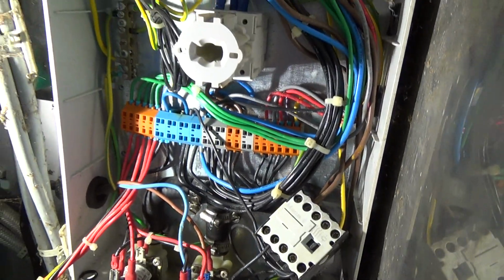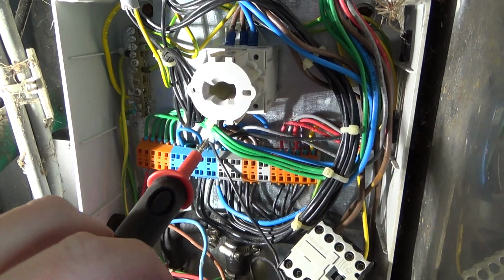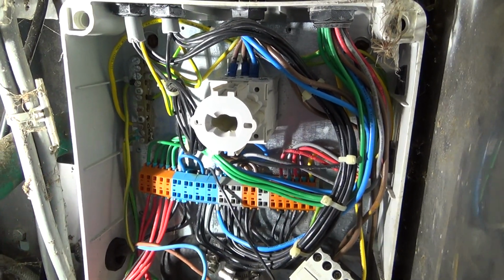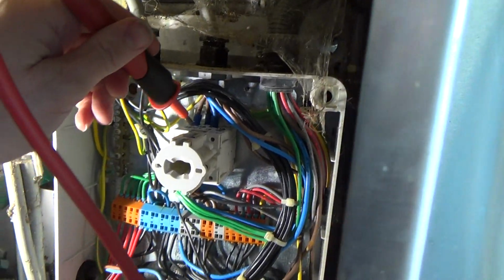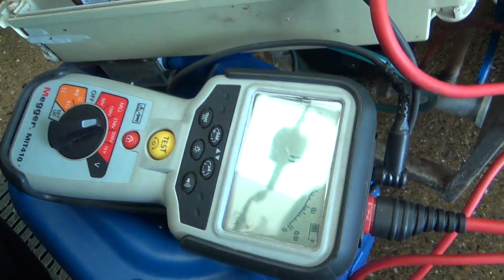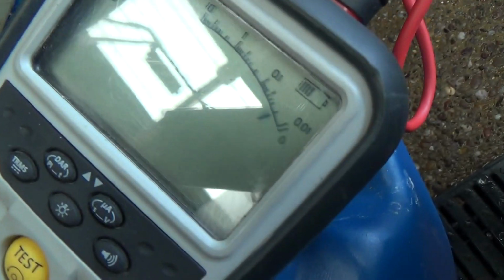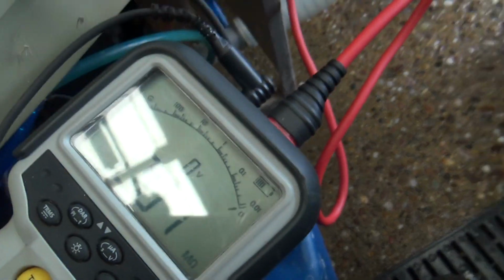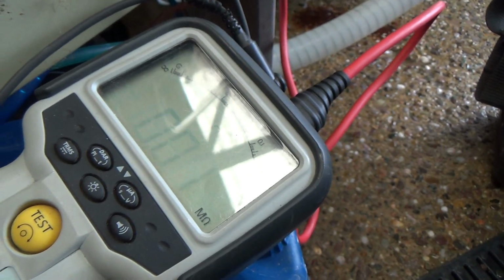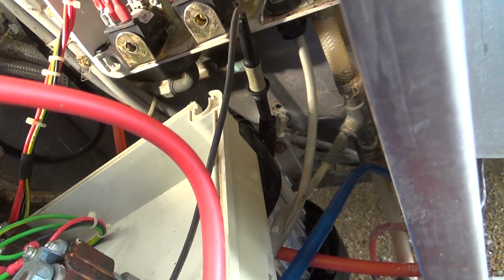Well, that's a thought. If there's bugs in there, they could be shorting it out. The power comes in on the switch on the bottom, which is unconventional. Generally, we expect the power to come in on the top. Nothing on there. Let's press the test button. Let's confirm we've got a good earth, which we have. I've just put it on the ground wires on the motor housing.